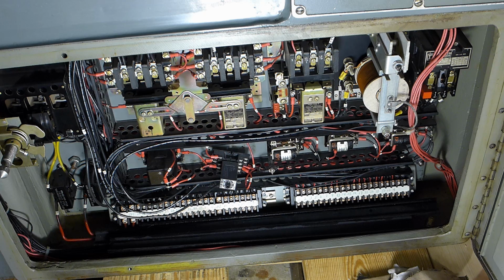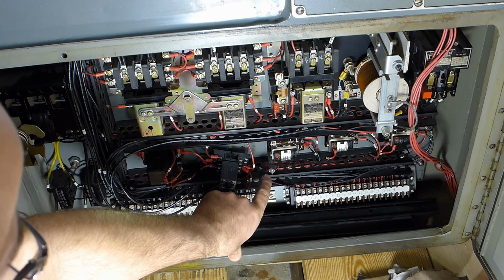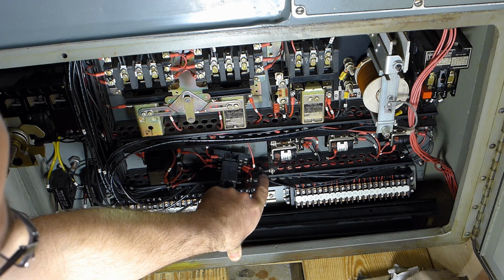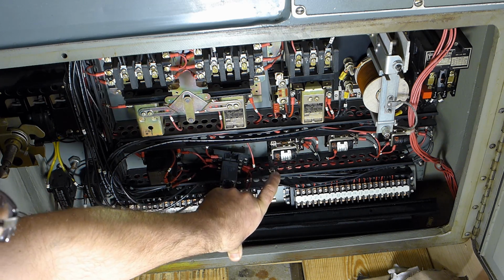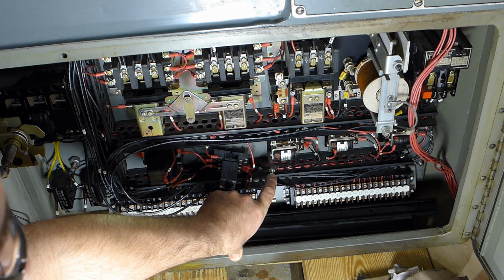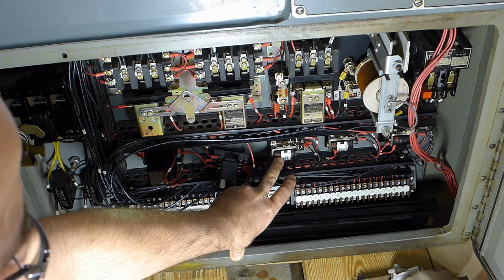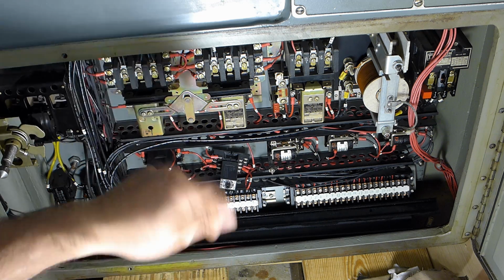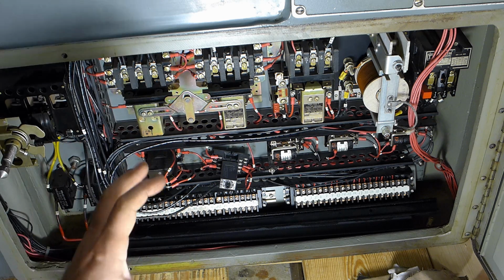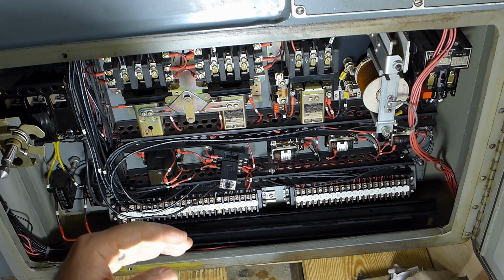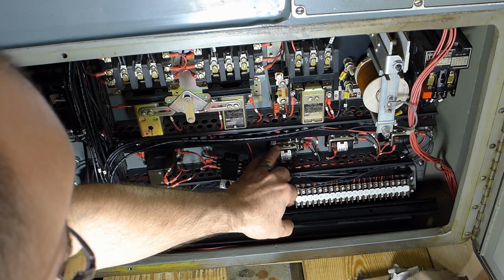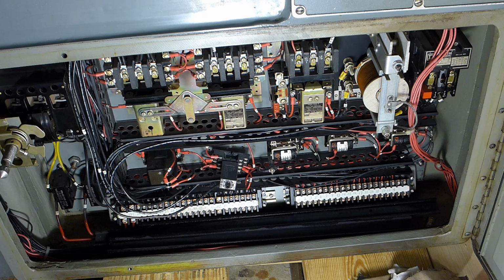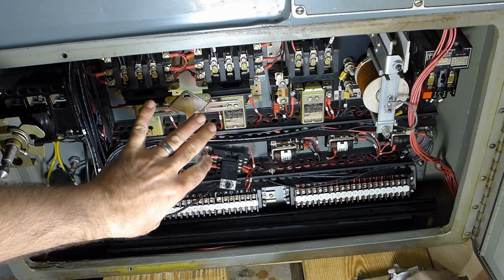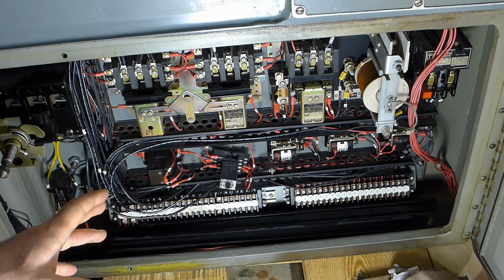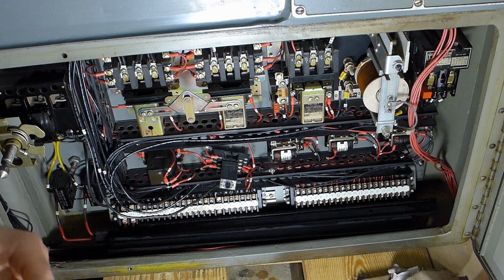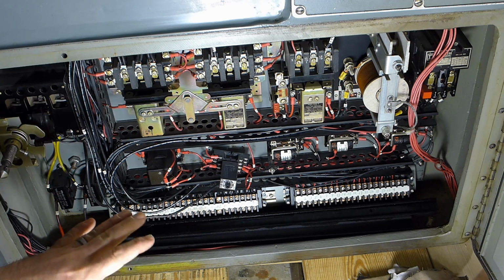Alright, so in here, the only problem I found was this ring terminal was broken on the original wire. That's the armature. It's A2 going to the anti-plugging relay, and so this is what you can have it at 4,000 RPM forward and then flip it to reverse, and the machine will brake the motor, and then once it gets below a set RPM determined by the settings on this little tension adjuster here, it will allow the reverse contactor to engage to go into reverse. So basically it keeps you from engaging reverse while the spindle is moving forward. So I believe that was the only major issue in here.